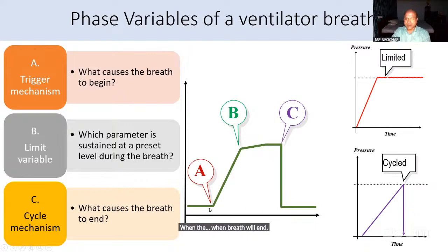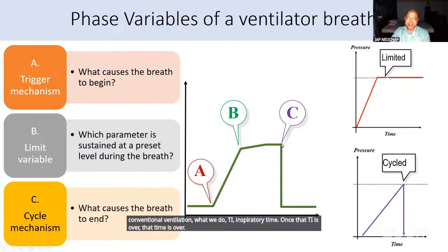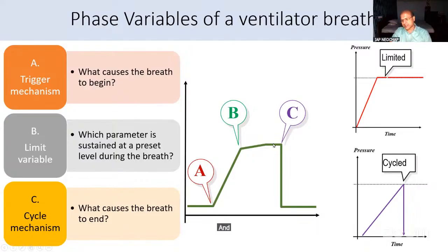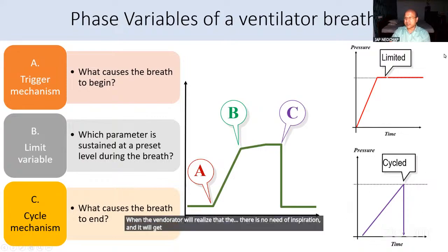So if you have given conventional ventilation, what do we do? TI, inspiratory time. Once that TI is over, the ventilator will stop giving the PIP. It will come down to PEEP. And there is also a cycling mechanism like PSV. It depends upon the flow. When the flow in the circuit is coming down, the ventilator will realize that there is no need of inspiration and it will get cycled. It will stop giving the breaths. That is called flow cycled.